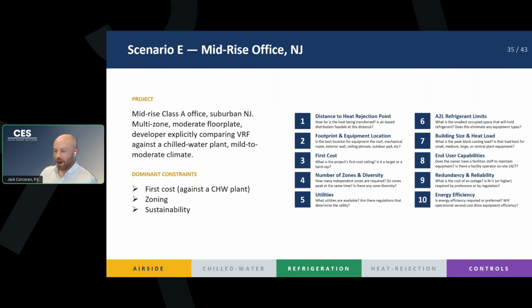Perhaps this office building, it's in New Jersey, right? We're not going to see those extreme temperatures of upstate New York. So maybe you're comfortable with having the heat pump heating as your only source of heat. You don't need a boiler. You don't need backup electric. The owner is basically choosing in this situation between having a central plant and running water throughout your building, or having rooftop equipment and having refrigerant run throughout your building. So those really come down to your two points.